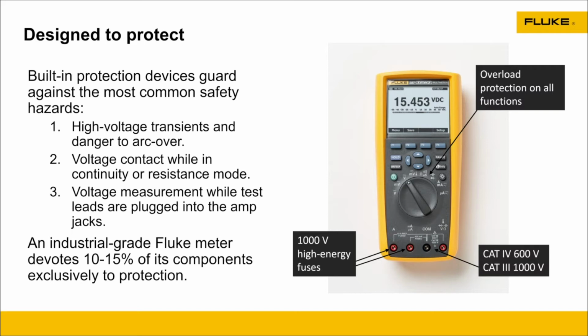I like to tell a story about this. I got an email from a guy who was out on an oil platform in the Gulf. He sent me a picture of his meter and it was black. I mean, it was black. You could barely see any yellow from the holster. He said one of his technicians was trying to make a measurement with an 87-V, which is rated for 1,000 volts. He plugged it in, put it in volts, and went to make a measurement. Unfortunately, the technician didn't realize he was actually measuring 4,160 volts. The meter withstood the shock from that measurement, and that technician was able to walk away unharmed.